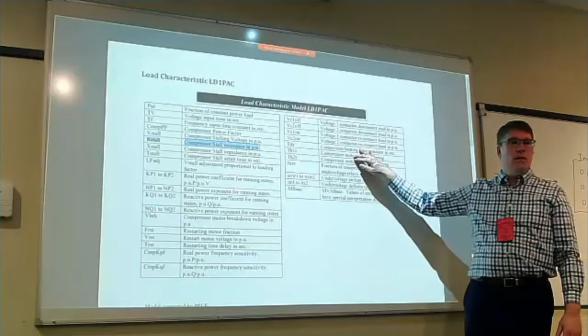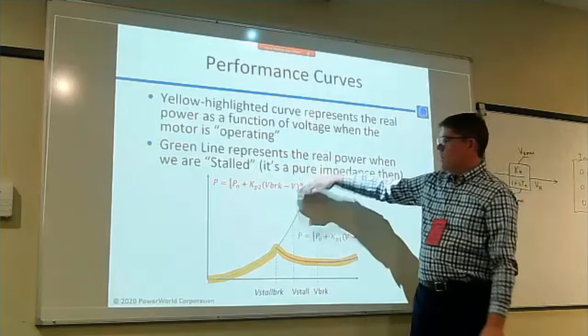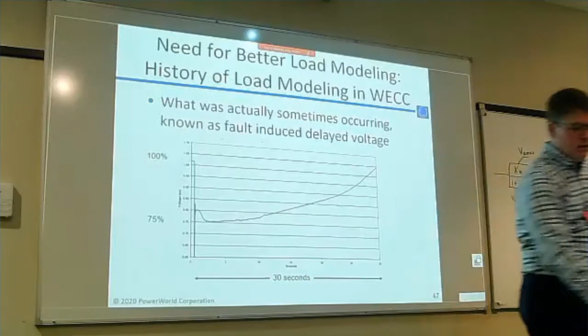This time constant is quite long. It's usually like 15 seconds. And it's what gives you this behavior. The reason it gives you this behavior with this load: voltage drops, these motors stall. They're now on that green curve. The voltage recovers, but because they're on that green curve, their loads went way up. So even though the fault is gone, the load at these particular motors just went up by a factor of 3 or 4. And therefore, the voltage stays depressed, hangs out there for somewhere around 15 to 25 seconds, and then the thermal relays finally start tripping them offline, and that's what gives you this response.